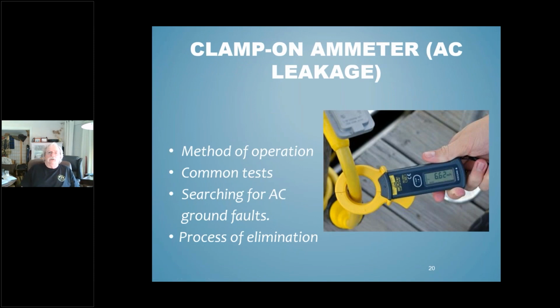All right, the clamp-on AC leakage meter. Again, I'm connecting this, and it looks like I'm using the meter the wrong way. I've got it around the entire shore power cord. That's the way you do want to use it. We're looking for a differential between the hot and neutral conductors. And in this case, I'm looking at 6.62 milliamps. Not necessarily a problem, depending on what equipment is turned on board the boat. It's not uncommon to see some low-level leakage, particularly on newer boats with digitally controlled power sources. They have some inherent leakage, which is normal.